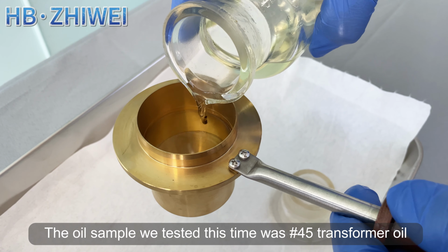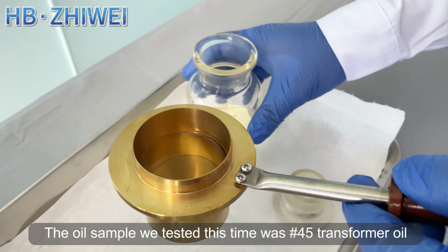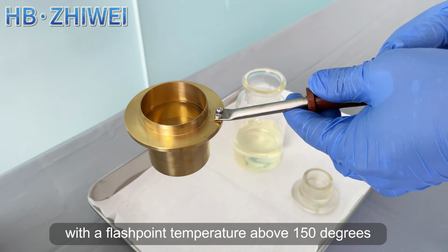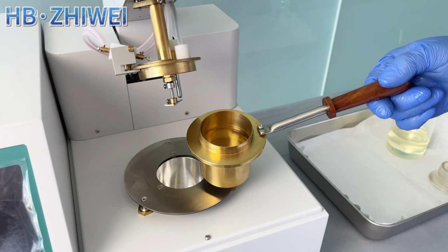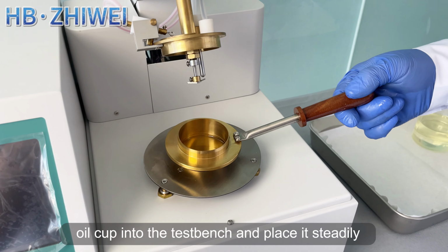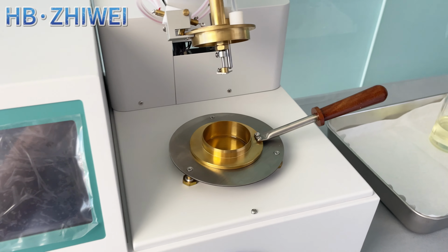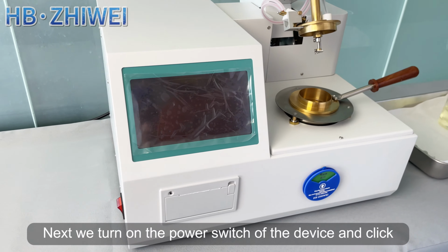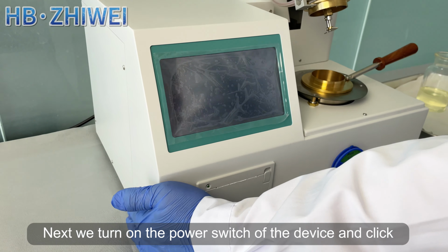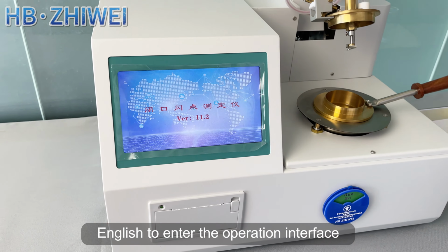The oil sample we tested this time was #45 transformer oil, with a flashpoint temperature above 150 degrees. We need to put the oil cup into the test bench and place it steadily. Next, we turn on the power switch of the device and click English to enter the operation interface.